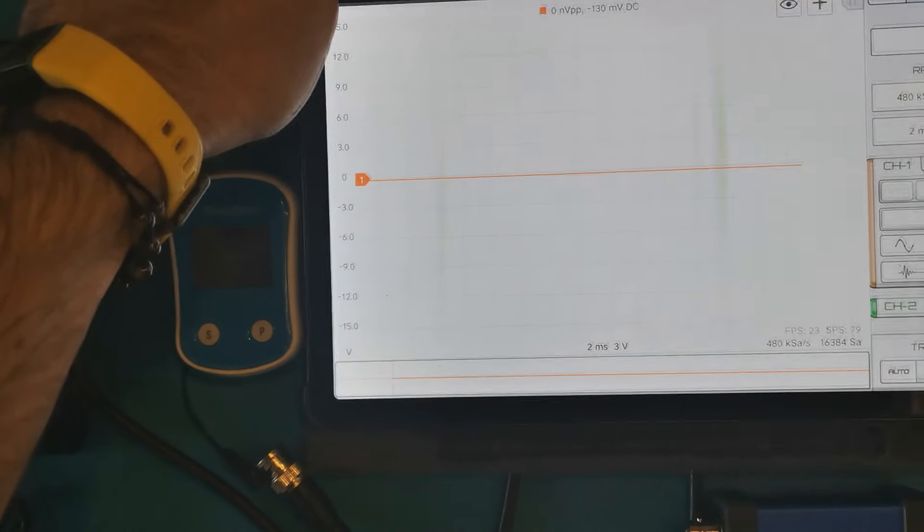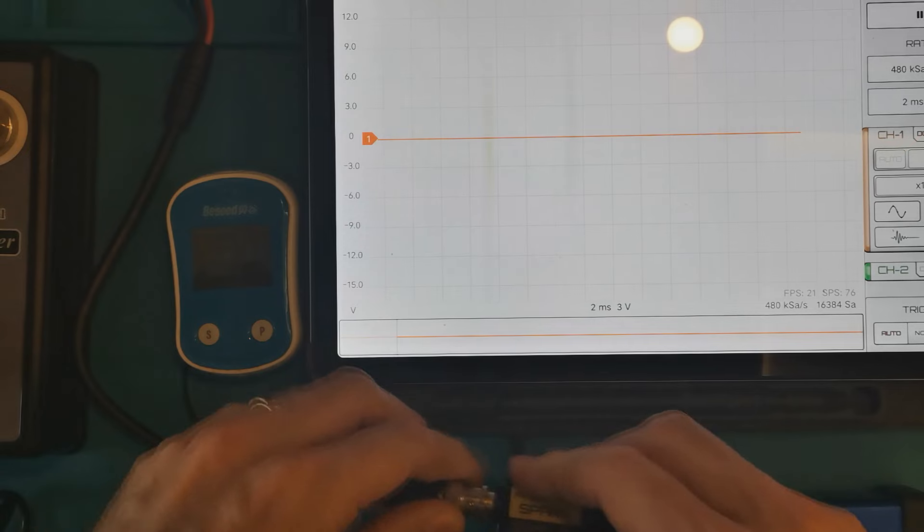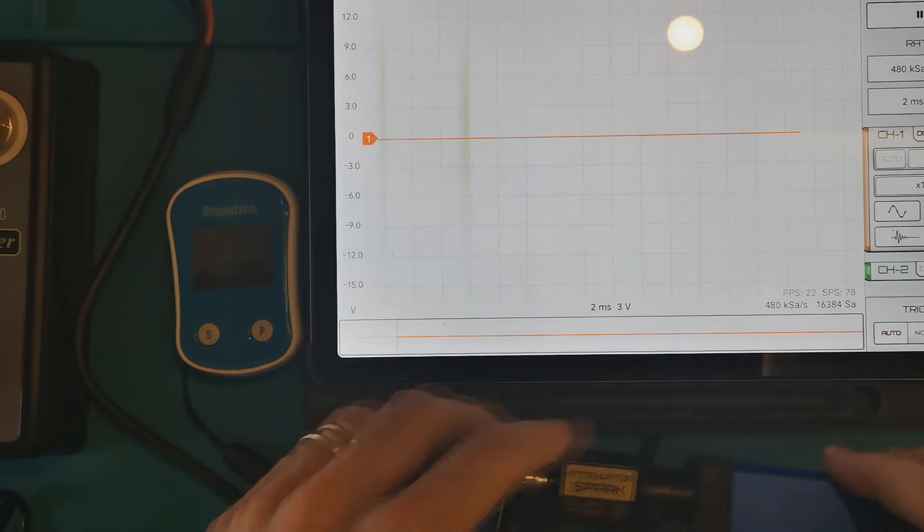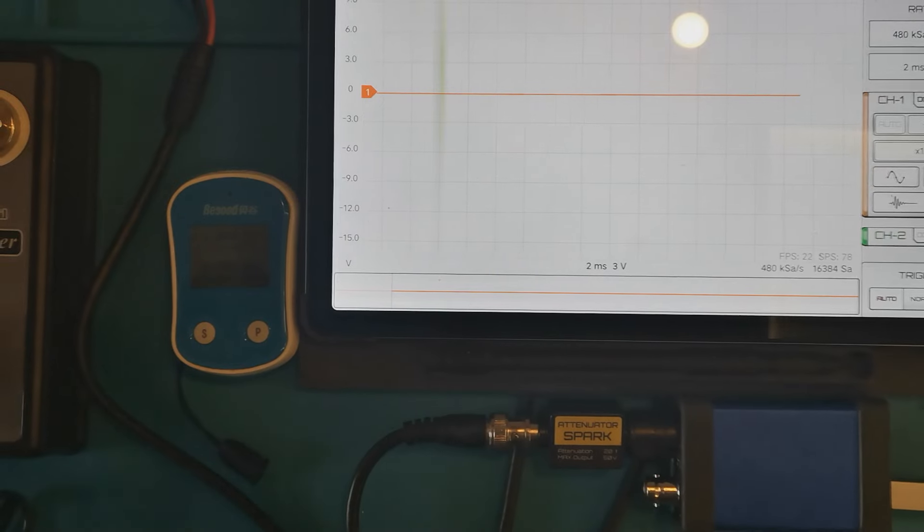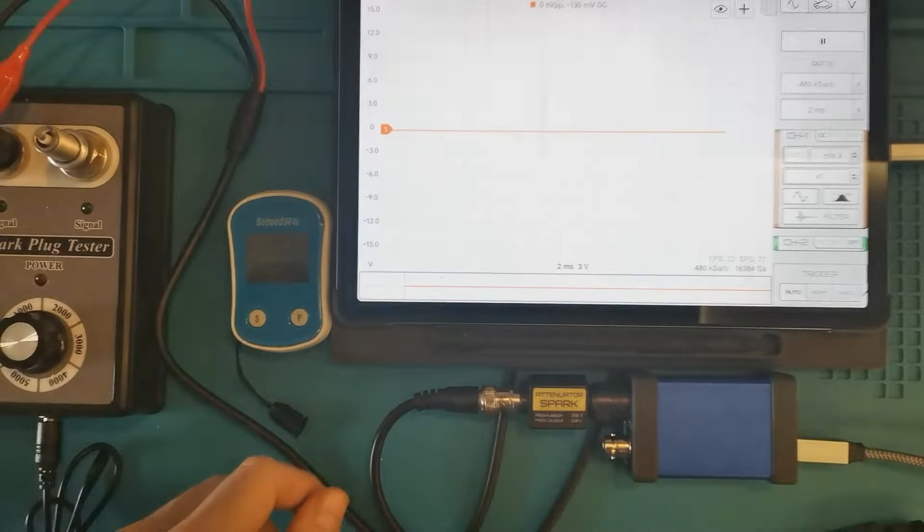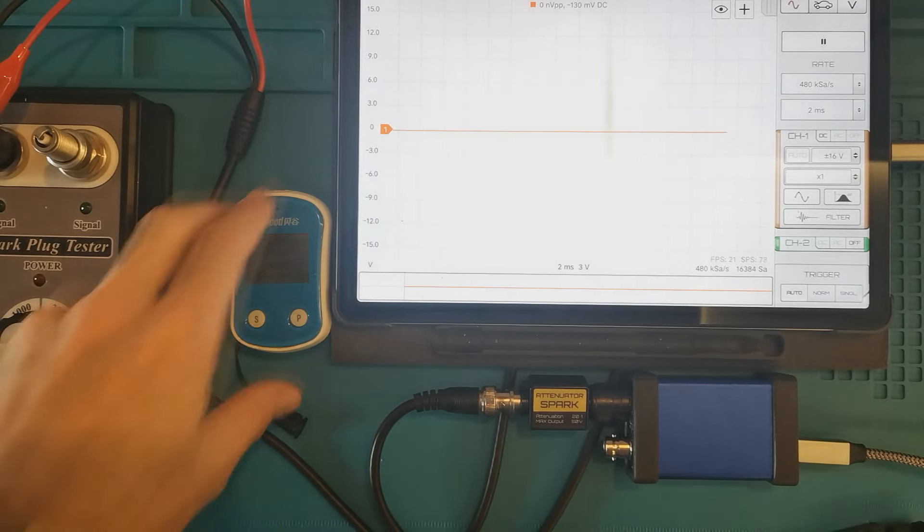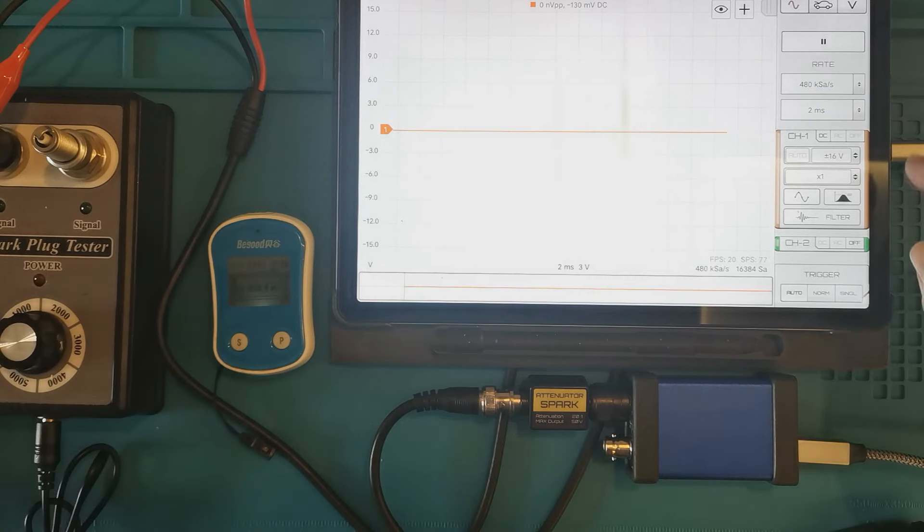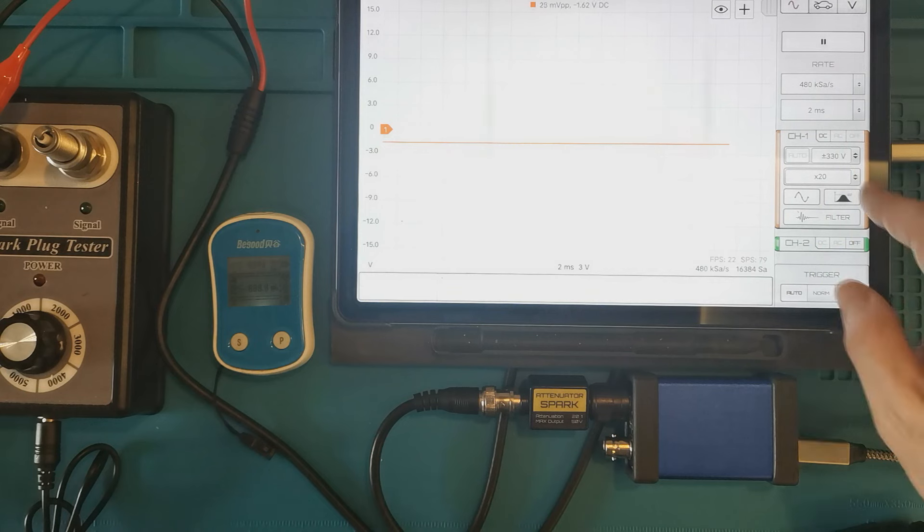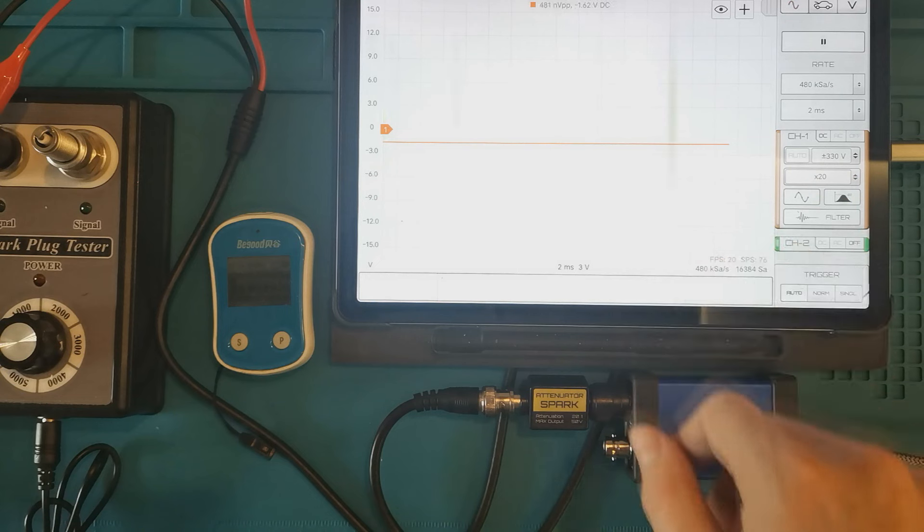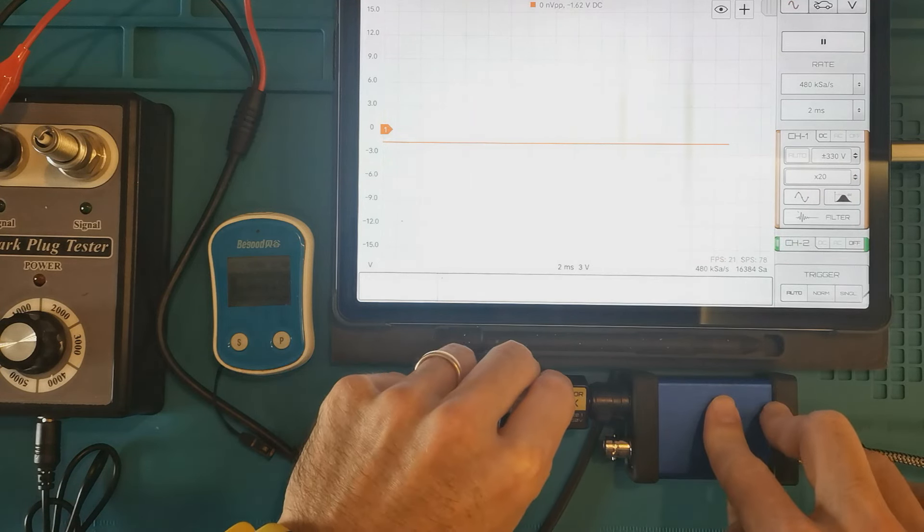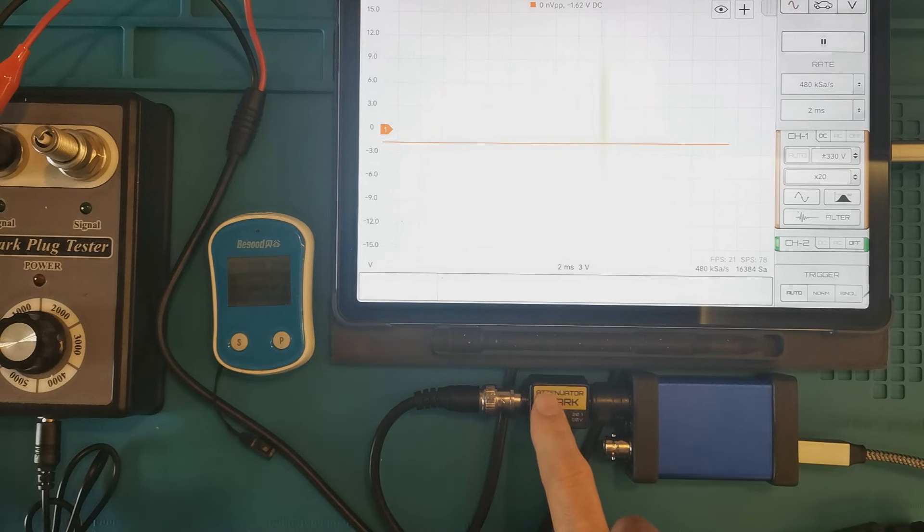Okay, I have my tablet running HScope. Let's see if I have a space to place the attenuator. Zoom out a bit. Okay. Let's set the probe to the factor 20 for the attenuation and run the spark directly inside this attenuator.